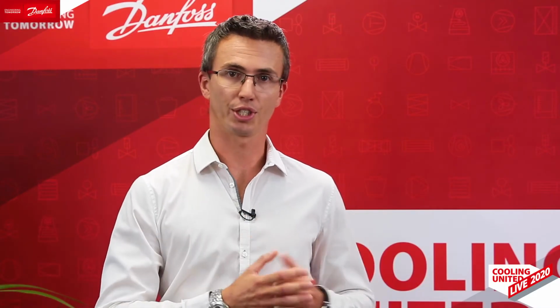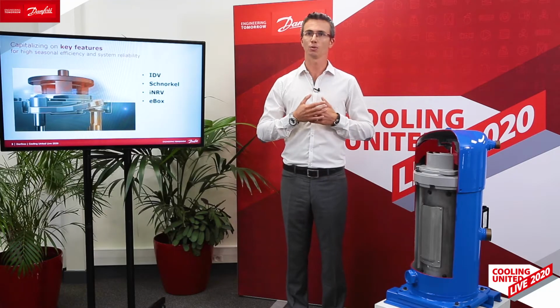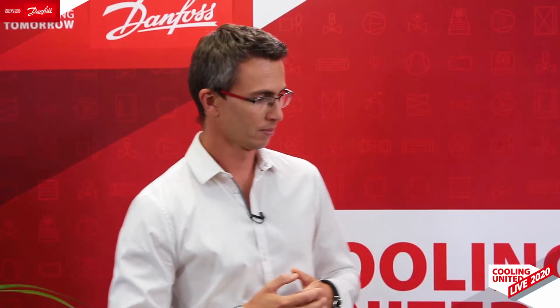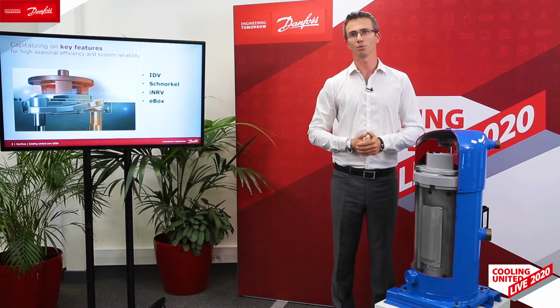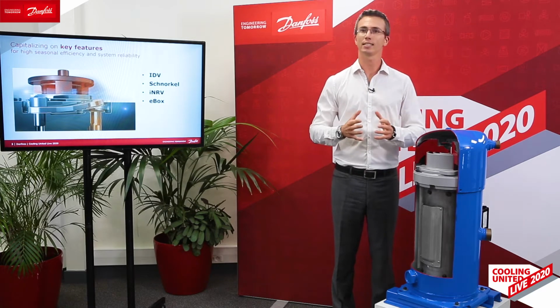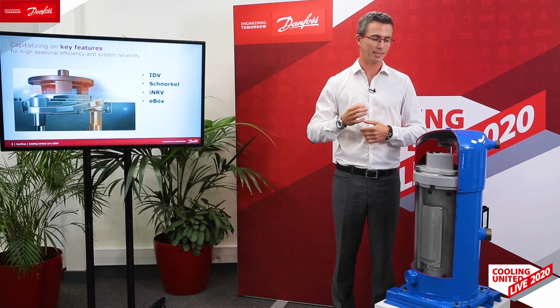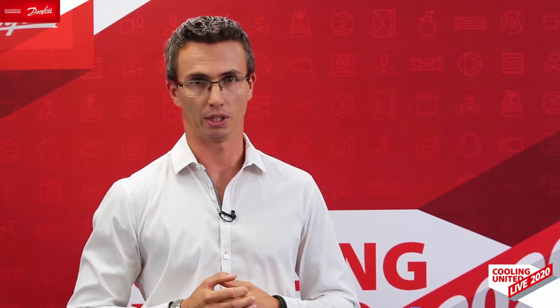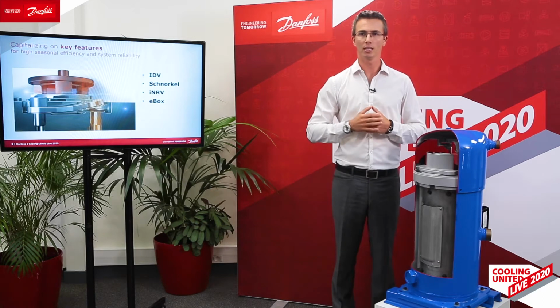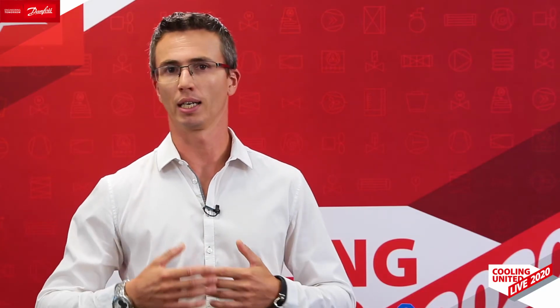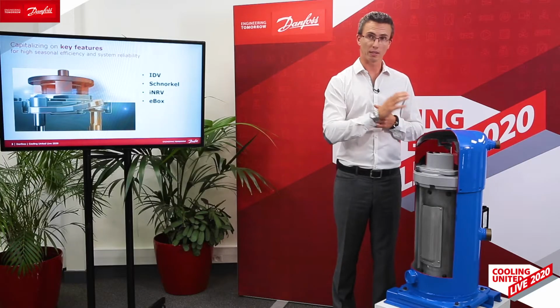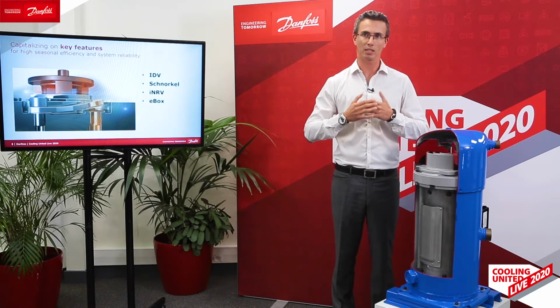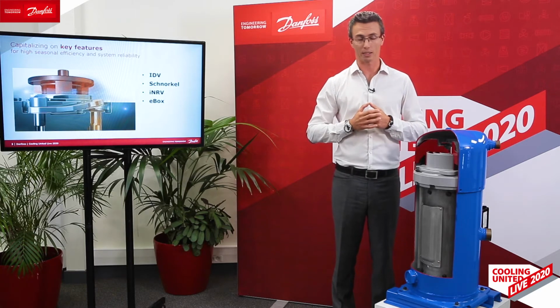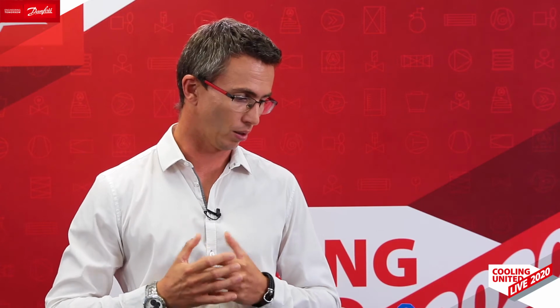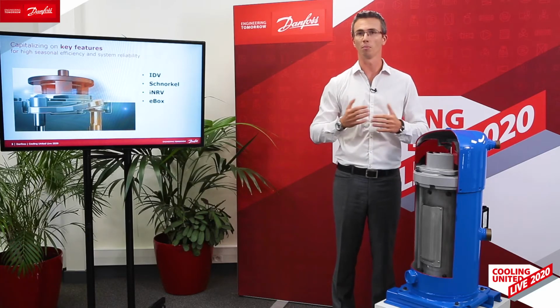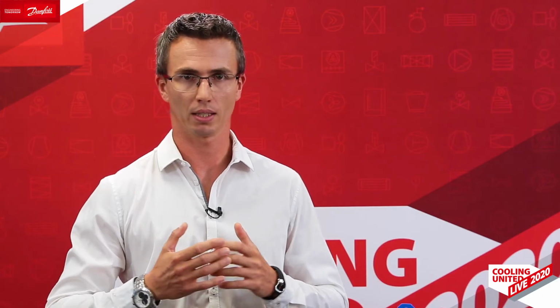First, let's have a look at the common features and to show you how it's fully dedicated to the next generation of applications. Starting first with IDV, that we have in our range since 2013 and which is targeting high seasonal efficiency because it's especially good in operation at part load condition. At part load condition, this device opens and releases the pressure, avoiding overcompression and avoiding loss of efficiency. For the same reason, this device helps reducing the mechanical constraint on the parts, which is especially good during startup. And on top of that, this is also good for liquid management, as in case some liquid comes to the scroll set, it opens and releases the pressure.